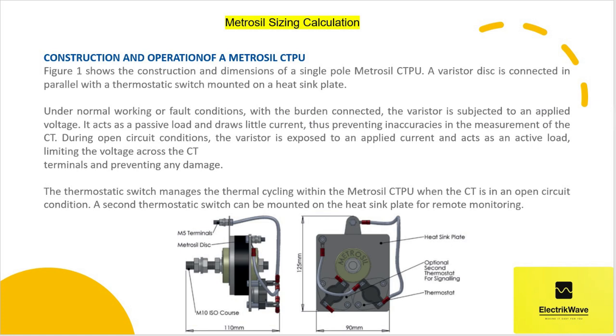During open circuit conditions, the varistor is exposed to an applied current and acts as an active load, limiting the voltage across the CT terminals and preventing any damage. The thermostatic switch manages the thermal cycling within the Metrosil CTPU when the CT is in an open circuit condition. A second thermostatic switch can be mounted on the heatsink plate for remote monitoring.